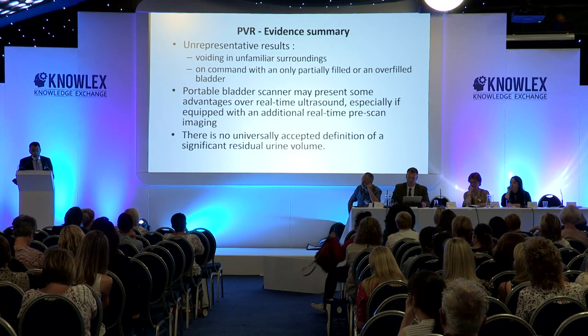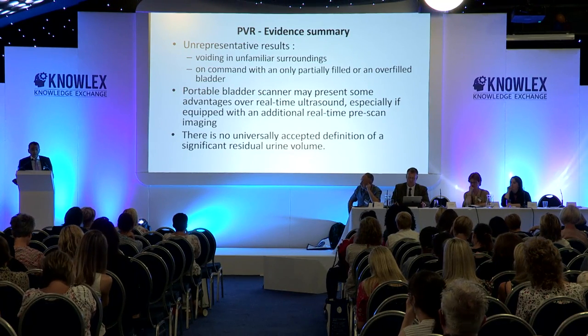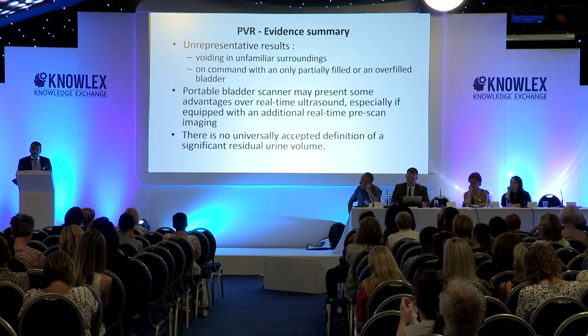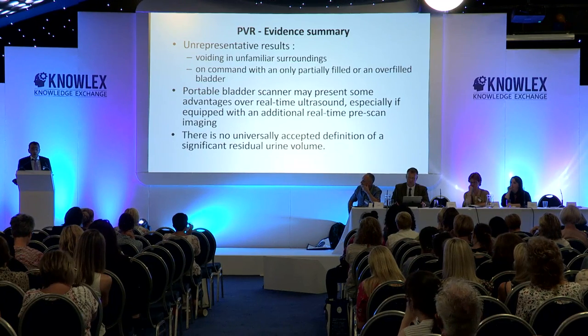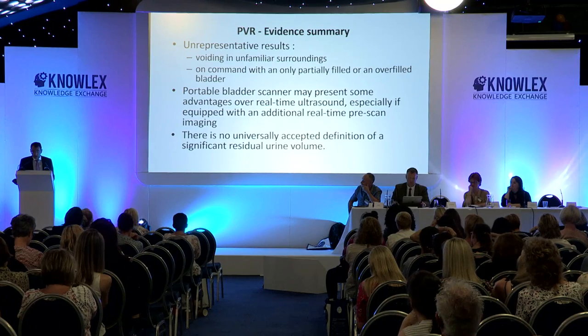Sometimes the bladder scan doesn't give you the right result. Patients may try to pass urine in an unfamiliar hospital environment and may not be able to, or may be in a rush, or their bladder may not be full. Using a real-time live scanner gives more advantage than a simple number-only scanner, although it requires more training.